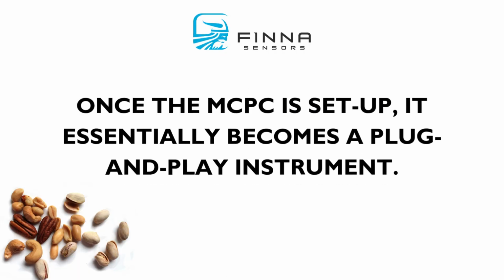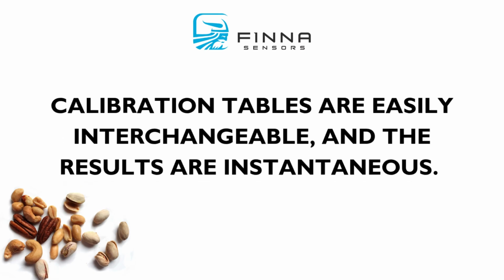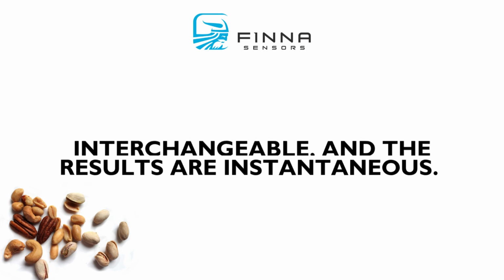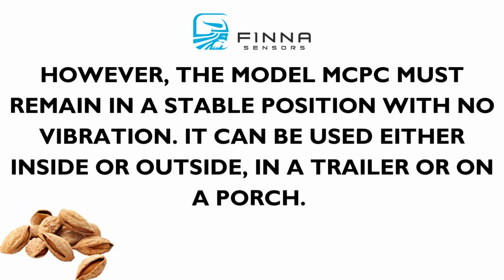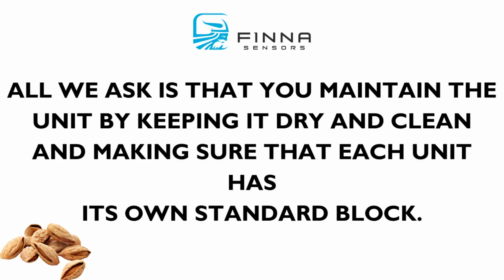Once the MCPC is set up, it essentially becomes a plug-and-play instrument, as I mentioned before. Calibration tables are easily interchangeable, and the results are instantaneous. However, the MCPC must remain in a stable position with no vibration. It could be used either inside or outside, in a trailer or on a porch. All we ask is that you maintain the unit by keeping it dry and clean, and making sure that each unit has its own standard block.